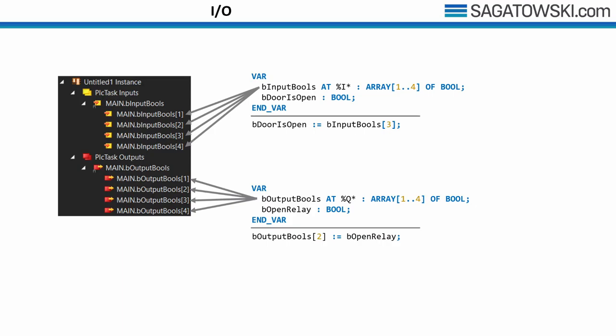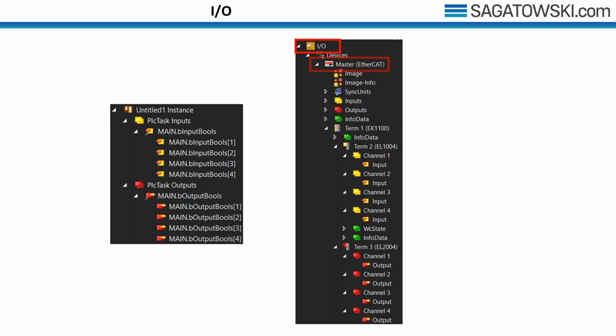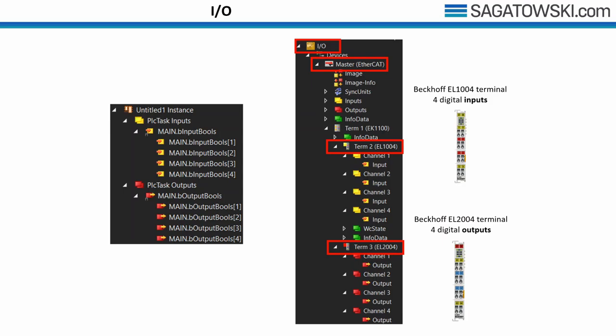The final step to close the loop is to link the variables to the actual hardware. All real-time capable hardware is presented in the IO object in the TwinCAT solution. This requires an EtherCAT master where we can define our terminals — in this case the EL1004 and EL2004. These two objects represent the actual physical devices. Inputs are shown with a yellow icon and outputs with a red icon on both sides — in our code and in the IO tree.